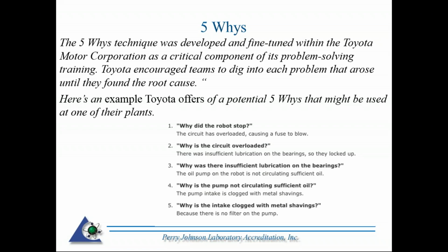Why is the circuit overloaded? There was insufficient lubricant on the bearings, so they locked up. We'll take it a little further. We could add some more lubricant there, but that's not going to prevent it from happening again.